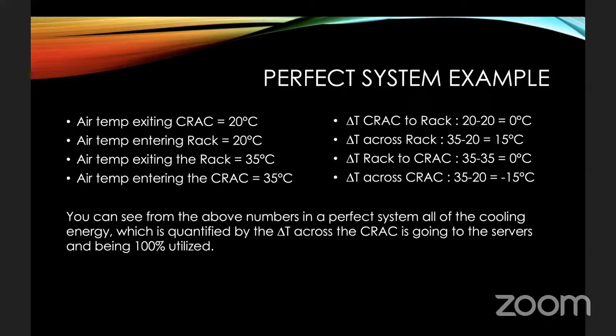Then we have the rack to the CRAC. It's 35 exiting the rack. It's 35 entering the CRAC. So again, that is a 0 degree delta T. And then across the CRAC, we have 35 to 20, which is a drop of 15. So you can see here, the drop of 15 across the CRAC is directly corresponding to the increase of temperature across the rack. So this is a 100% efficient cooling system, a perfect example.